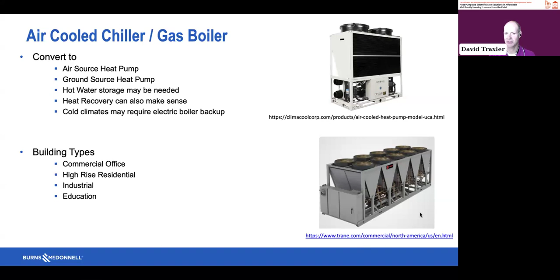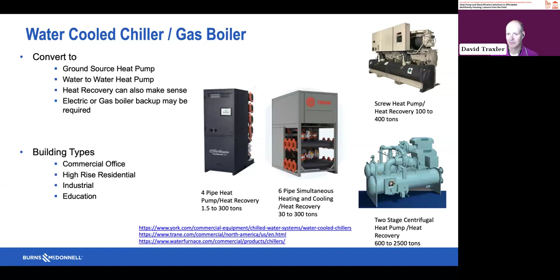The final system is the water-cooled chiller and gas boiler. For water-cooled chillers, you have water source heat pumps or water-cooled heat pumps. Larger units over 600 tons of heating and cooling are shown on the right, suited for high rise or large multifamily buildings. For smaller multifamily buildings, there's a smaller size, about the size of a refrigerator, that you can stack together. You need an energy source for those, typically the ground or a supplemental heating source, if you switch out to a water heat pump.